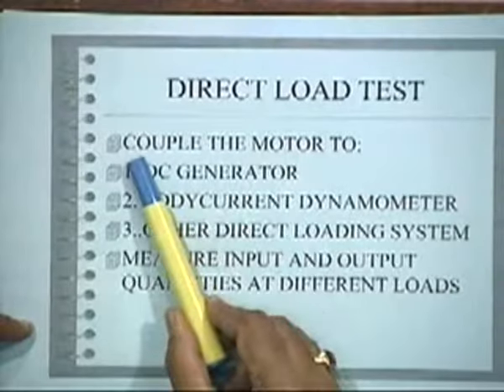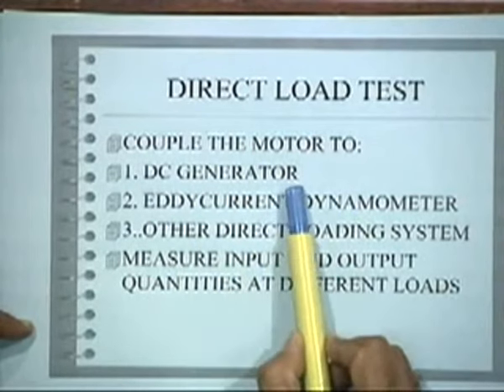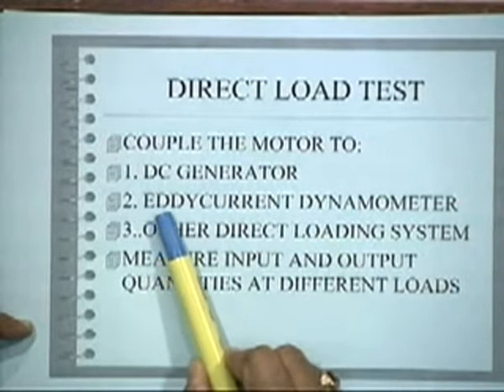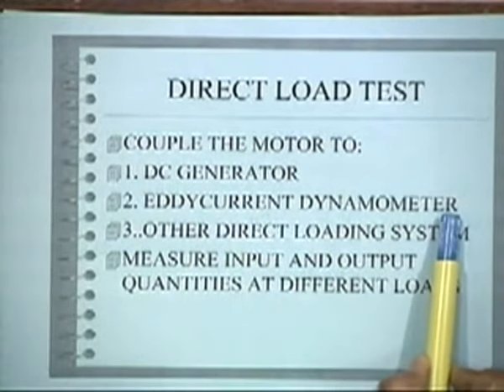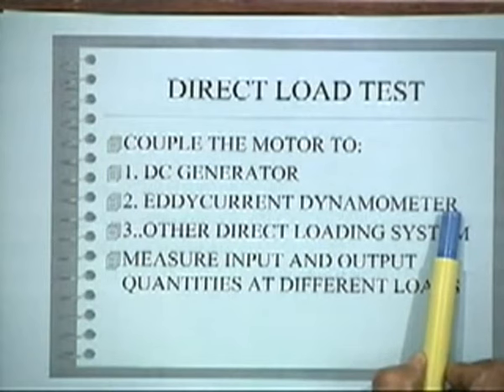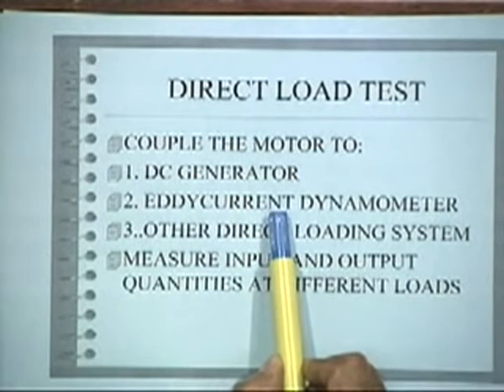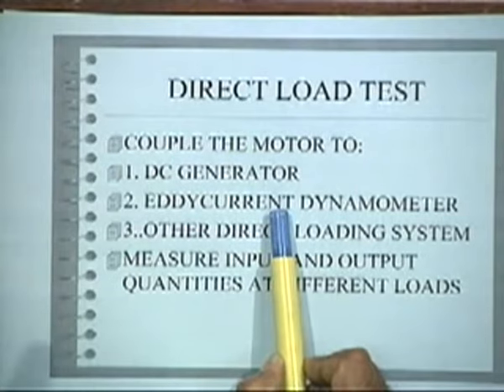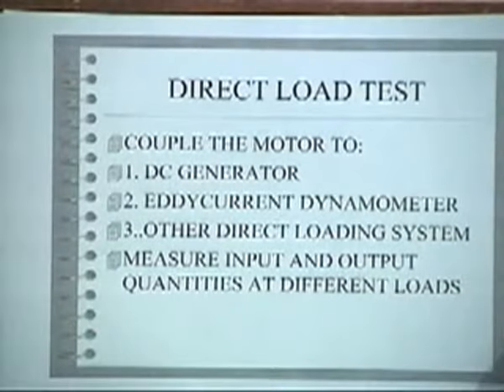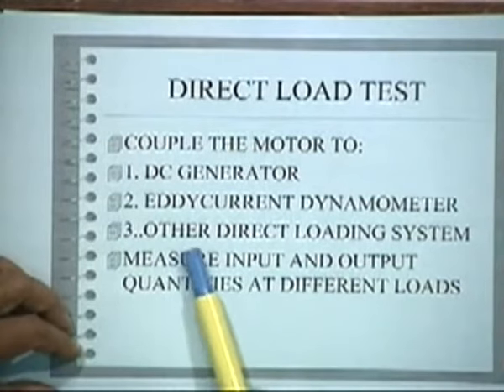That is one of the procedures. You want to see how it will behave under load. So you couple the motor to either a DC generator or what is known as a dynamometer. Dynamometers are loading devices, and there are different types. One is called the eddy current dynamometer, where you pass a current through a coil in the stator, and the rotor is made of eddy current material. The higher the stator current, the more the eddy current, so the opposing braking torque will be more. Your whole purpose is to load the motor, or you can have other direct loading systems.